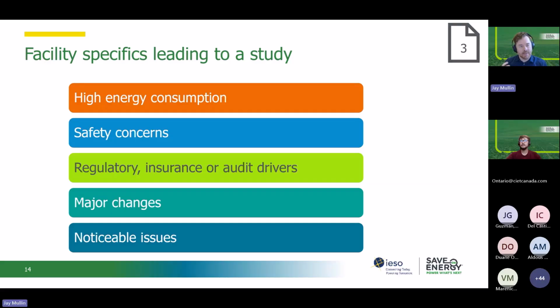A lot of times people think that air balancing is only worthwhile if you have a building automation system that can control and adjust to address some of these issues. And that is very useful, but it can still be worth doing even if your facility has manual or standalone systems, like rooftop units, exhaust fans, and VFDs that can be manually adjusted based on the findings. Or if there are known comfort, indoor air quality, or pressure issues, doing that study can help quantify that and suggest changes to address those issues, even if those changes are manual controls.